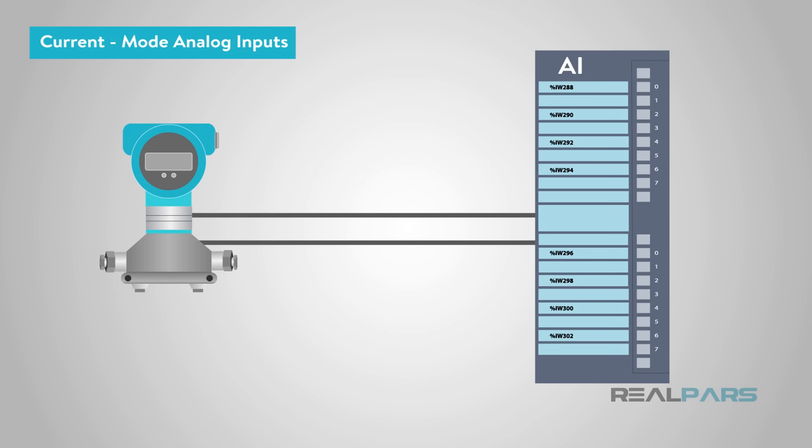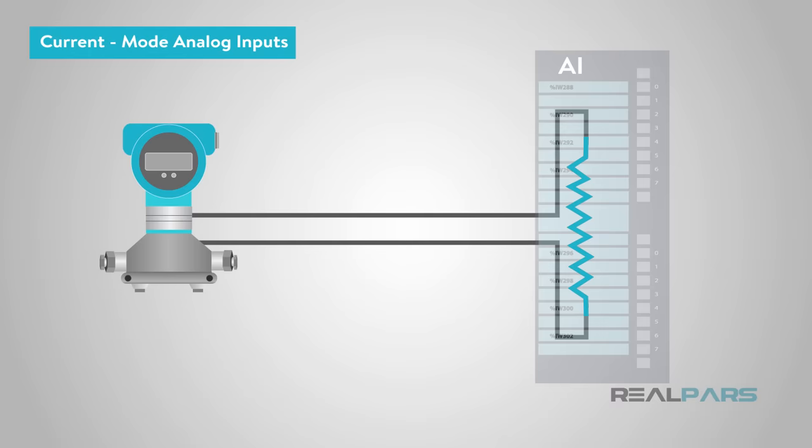From the PLC end, a current mode interface is generally a voltage mode interface with an added high-precision resistor. While the resistor is often inside the PLC module, and switched in by a jumper or connection position, it is effectively the same.